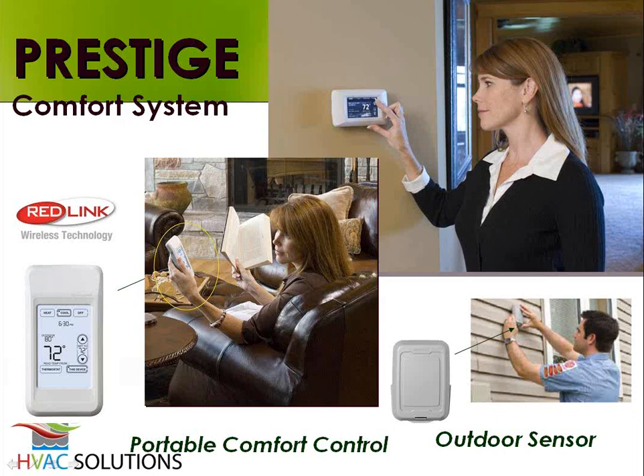So when I say it's wireless, kind of, the FocusPRO stats were completely wireless. They talked wirelessly to the equipment, and that was it. The Prestige stat is only somewhat wireless. So by that I mean the stat itself physically has to hardwire down to the furnace. However, it can support some of the wireless accessories. So in this case, it supports a wireless outdoor air temperature sensor.